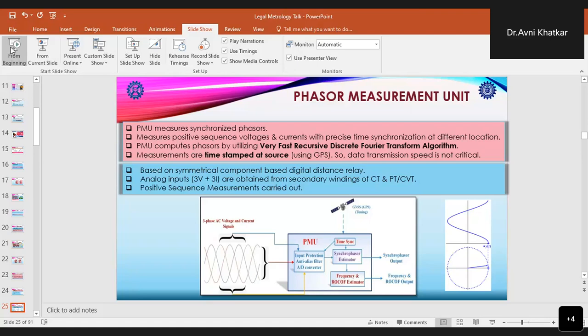So these PMUs which are developed measure synchronized phasors, and they measure the positive sequence voltages and currents, which have time synchronization at all the different locations, and they compute these phasors by utilizing very fast recursive discrete Fourier transformation algorithms. And as I've already told, they are time stamped at the source, so data transmission speed is also not critical, because all the measurements are time stamped at the source itself.